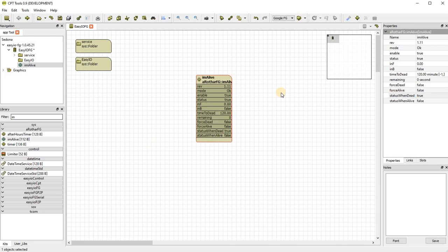Integration to VRF systems like Daikin or Mitsubishi or Hitachi, if you're doing that through your EasyIO controller. This is for that. Their devices through their gateways, the status for those devices aren't dependent on the gateway being up. So the device can stop communicating and you won't know.